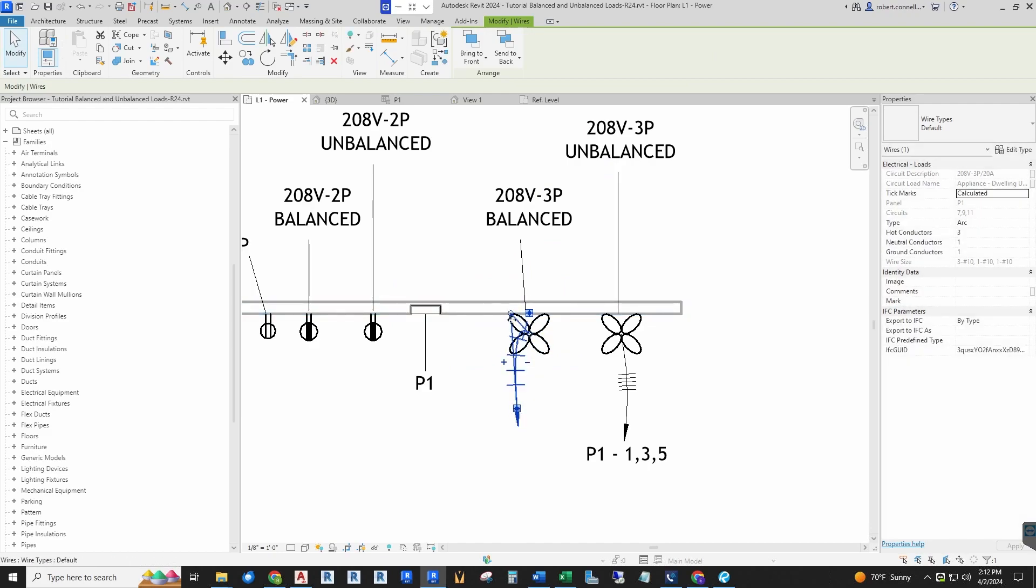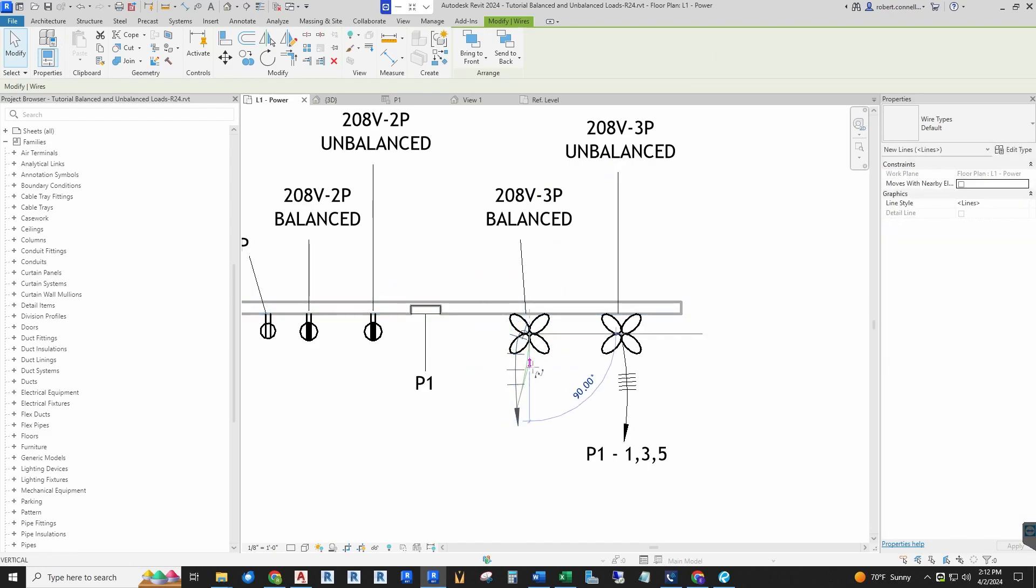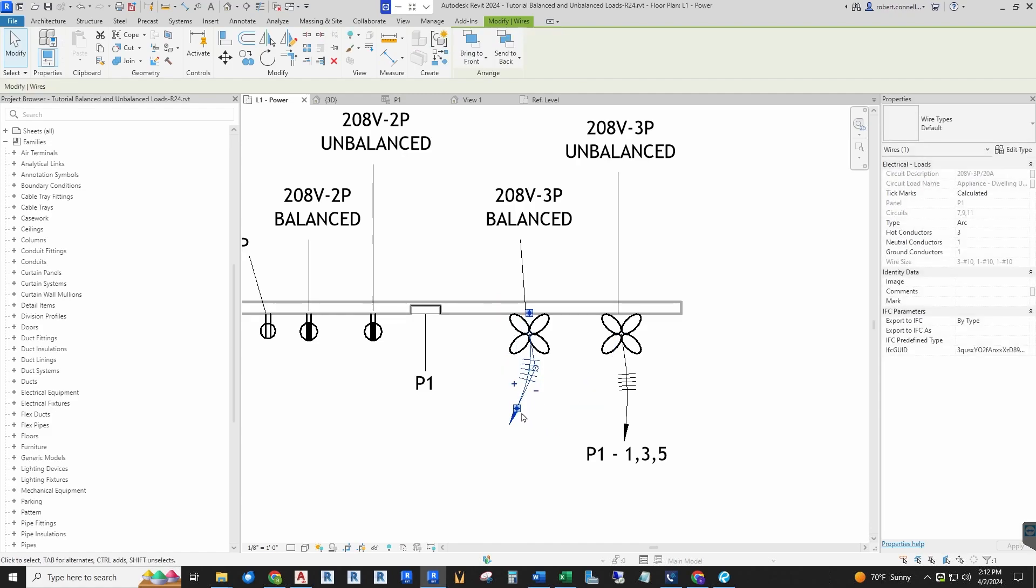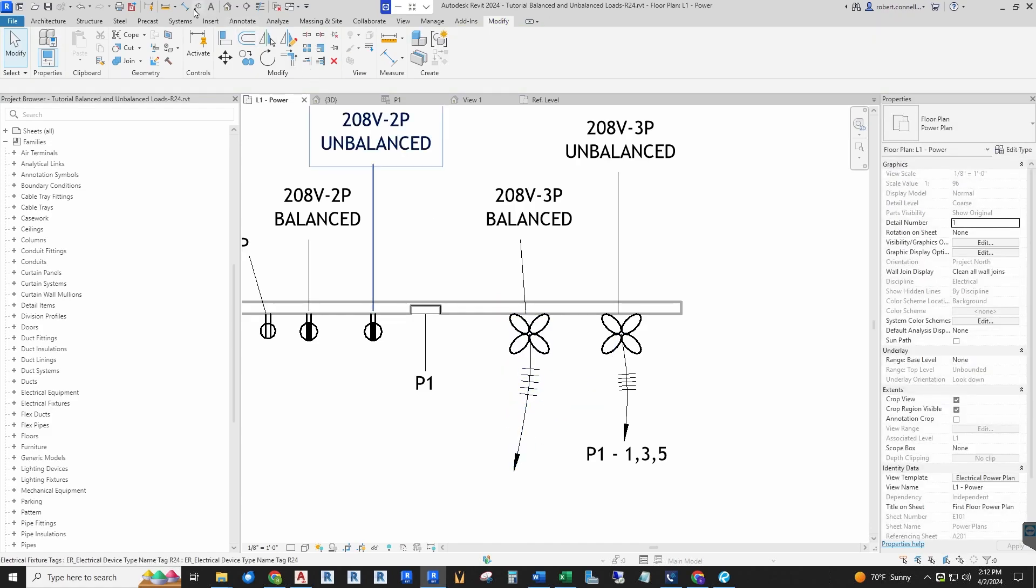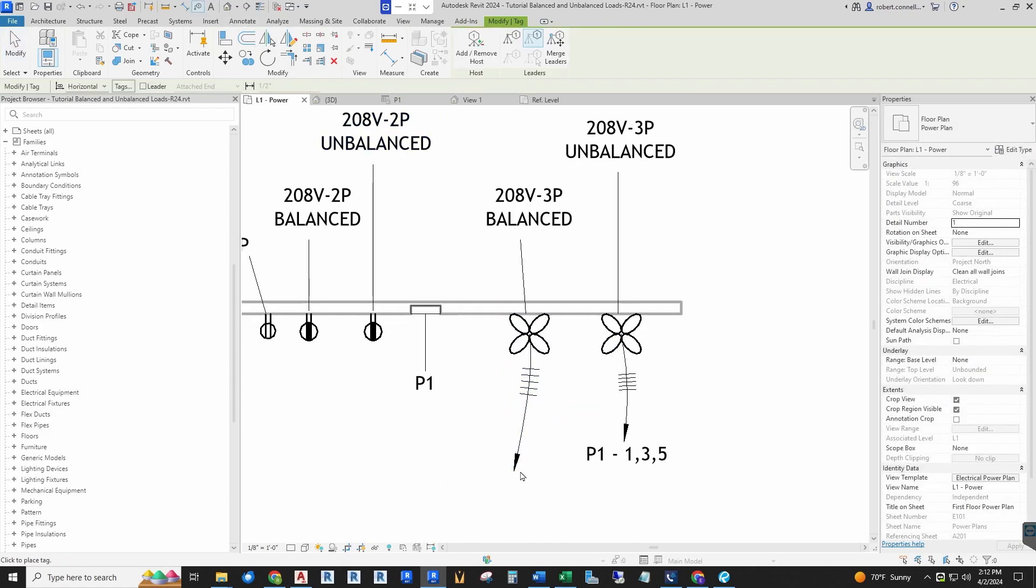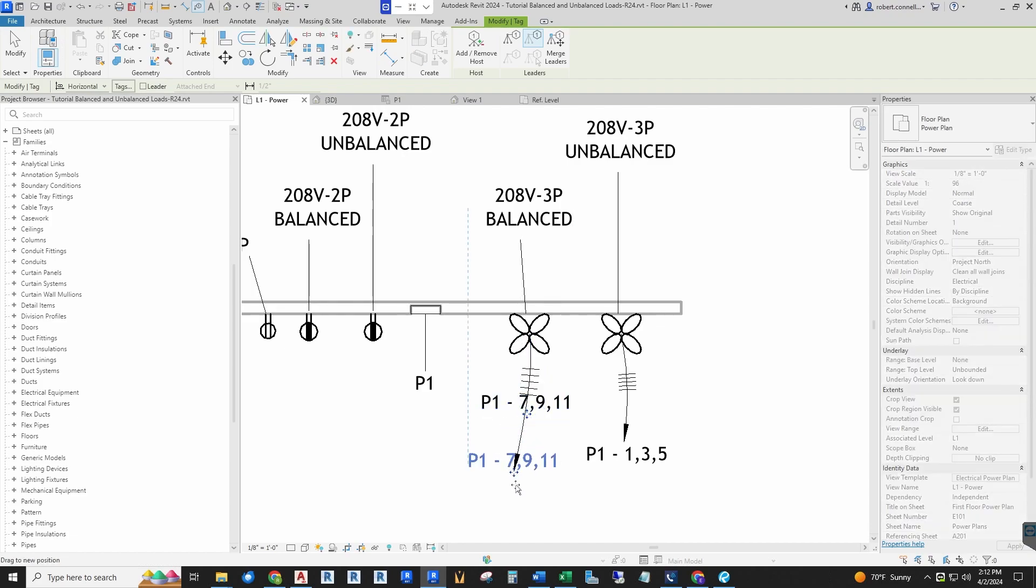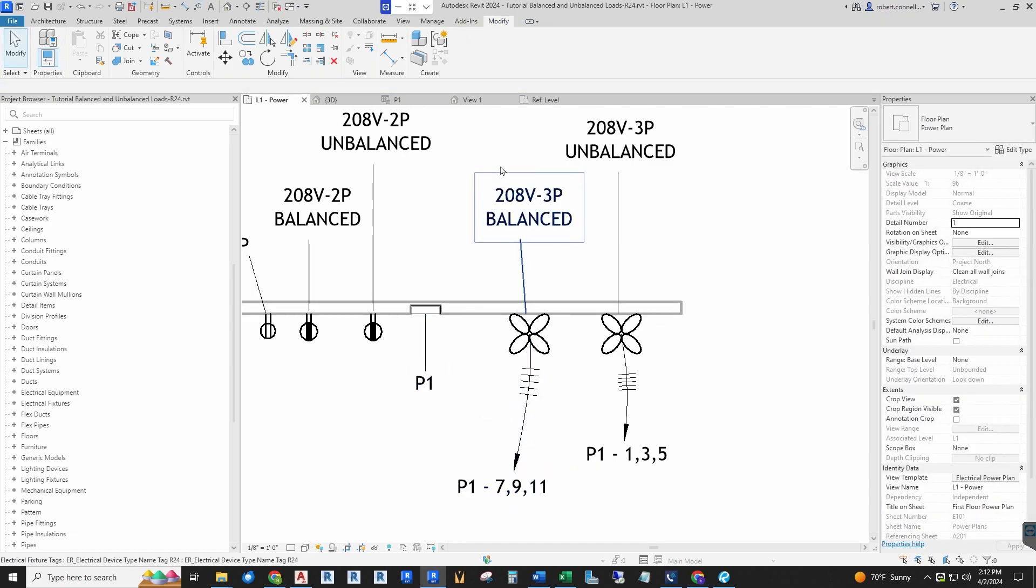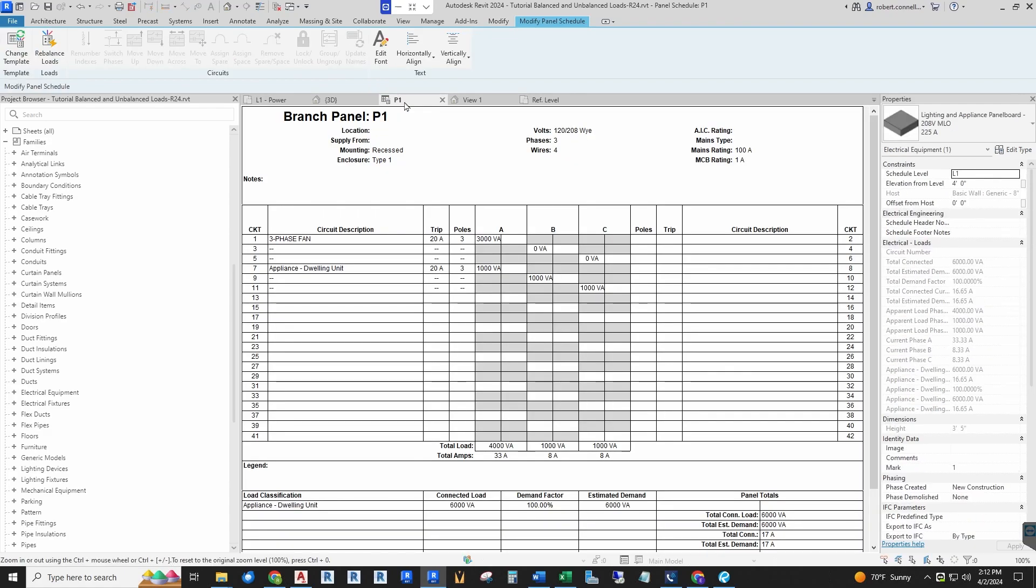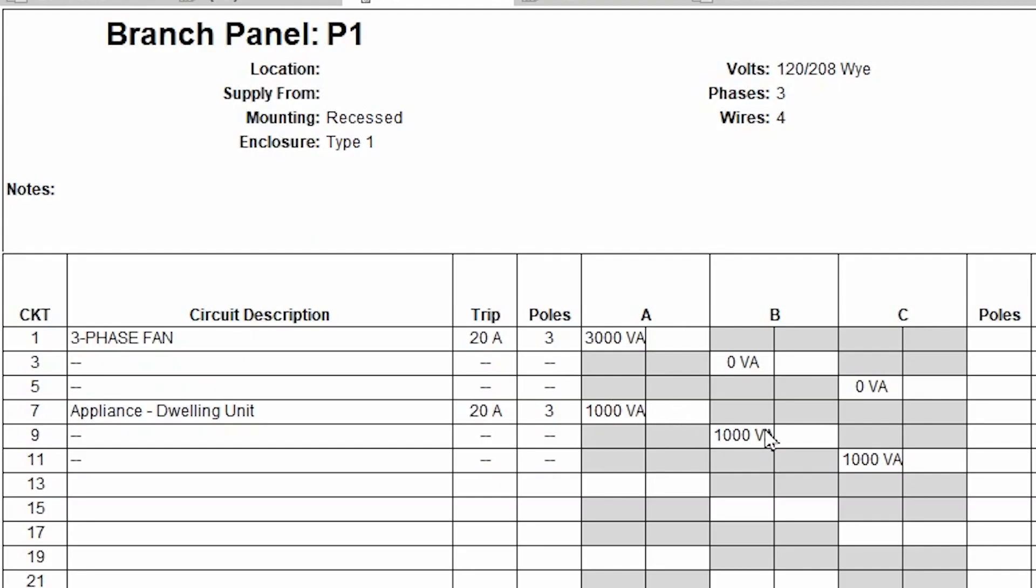It's going to automatically assign it the way I have it set up to assign in order. Let's go ahead and tag this guy. It is the next three circuits: 7, 9, 11. So let's see what happened—circuits 7, 9, 11. And there it took our 3kW and divided it amongst all three phases.